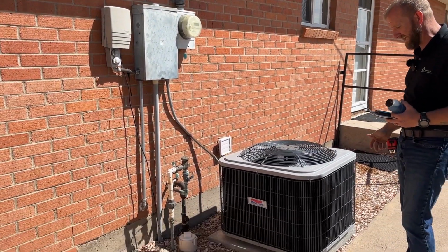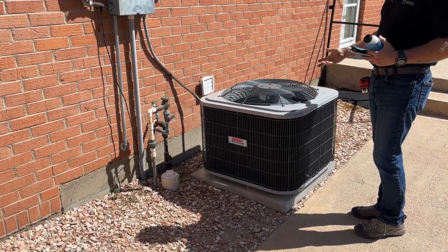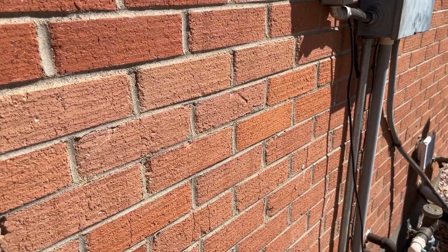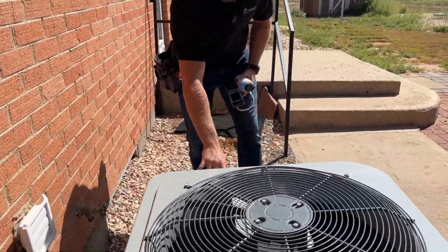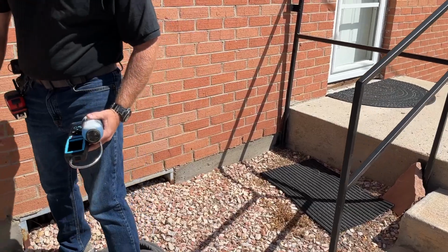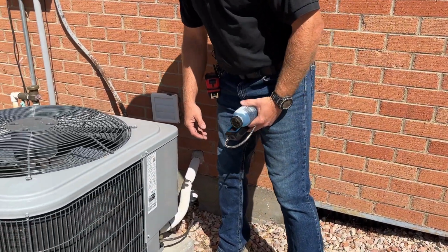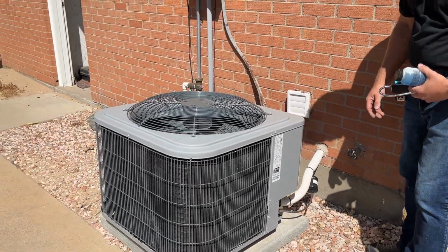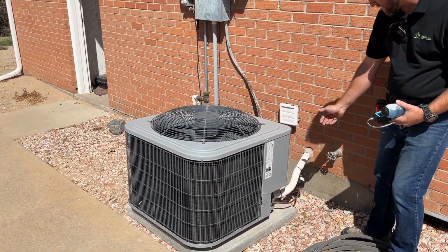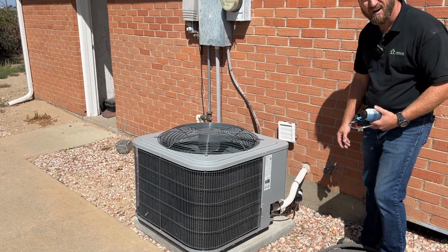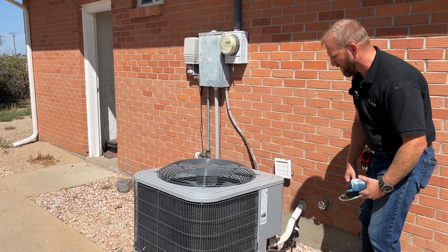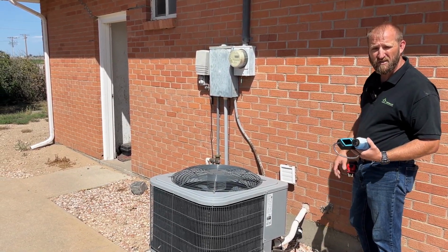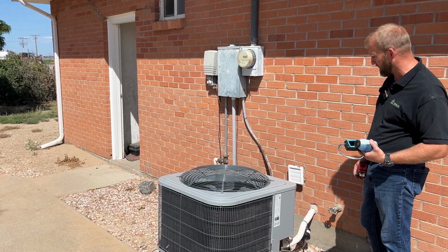Another thing we're going to look at is the age and the condition of the condenser unit. I know the other trainings have already gone through what you're looking for on the serial numbers for the units. This unit is really clean on the outside. This is just a regular air conditioner unit, not a heat pump unit. We're looking to see if there's insulation on the low pressure pipe for the unit. That can affect the efficiency and make the unit freeze up if it's not insulated properly.